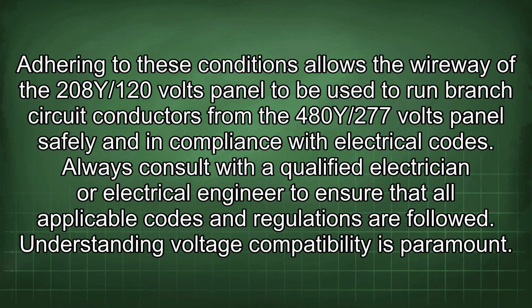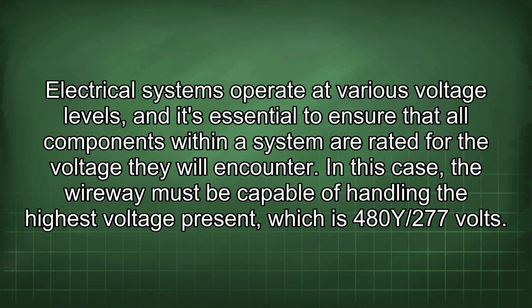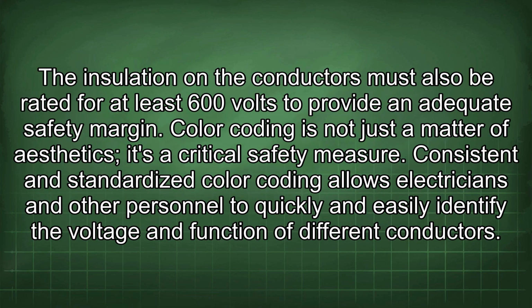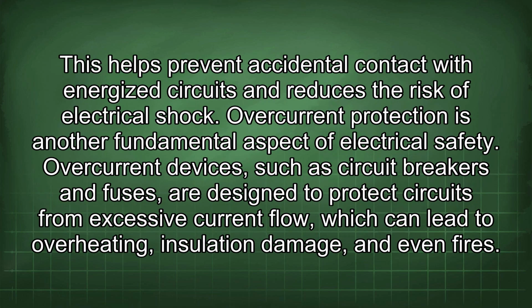Understanding voltage compatibility is paramount. Electrical systems operate at various voltage levels, and it's essential to ensure that all components within a system are rated for the voltage they will encounter. In this case, a wireway must be capable of handling the highest voltage present, which is 480Y/277 volts. The insulation on the conductors must also be rated for at least 600 volts to provide an adequate safety margin. Color coding is not just a matter of aesthetics, it's a critical safety measure. Consistent and standardized color coding allows electricians and other personnel to quickly and easily identify the voltage and function of different conductors. This helps prevent accidental contact with energized circuits and reduces the risk of electrical shock.